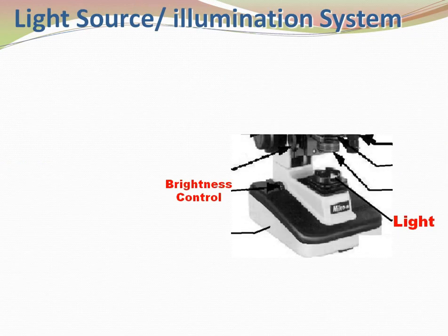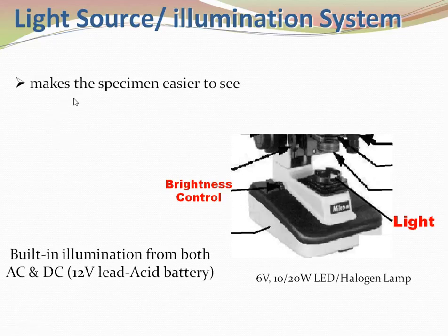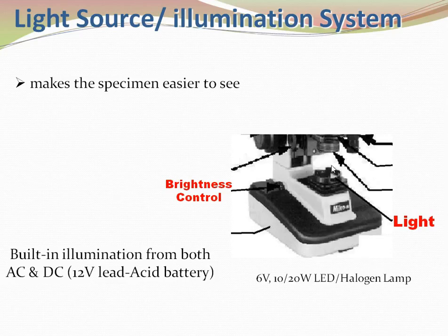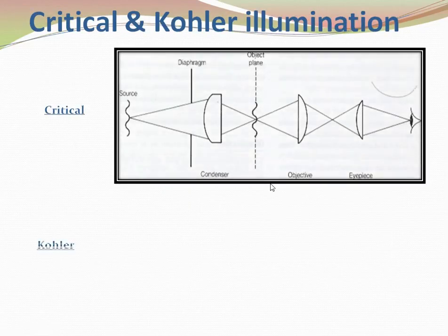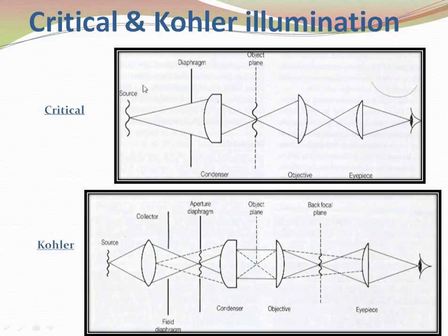Now the light source: LED white light is used with brightness control to increase or decrease brightness. The function of light is to make the specimen easier to see. Built-in illumination works from both AC and DC using an LED halogen lamp. It is mounted below the microscope on the base. There are two types of illumination: critical illumination and Köhler illumination.